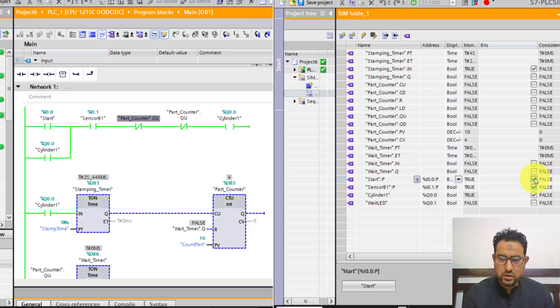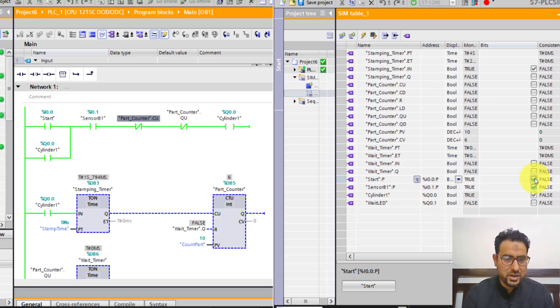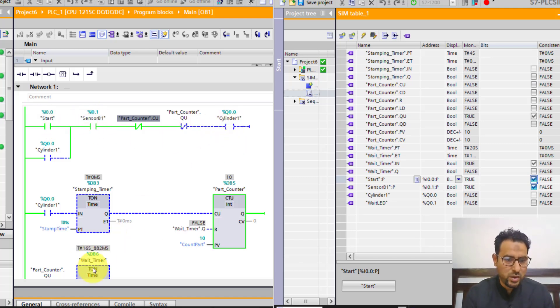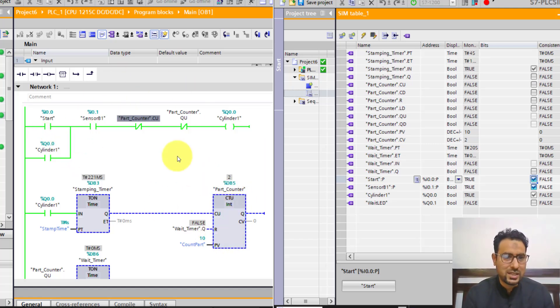If I do this for 10 times — that is the counter reaches 10 — the second timer will start timing. I'll keep the start button pressed so things go quickly. The counter is now at seven, eight, nine, and then 10. Once it reaches 10, you can see the wait timer is now running, the switch has turned off, and even with start pressed and part present, the cylinder is not turning on. After the wait timer completes, the counter resets to zero and the whole process can begin again.